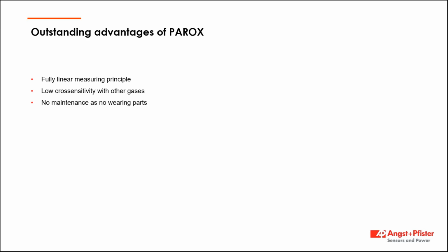Of course, you need calibration from time to time, but this very much depends on your application. You have a very long lifetime. When a sensor is running in steady conditions and with well-filtered air, it runs for years and even tens of years. You have precise measuring in the volume percent range. If you are looking for a real ppm application, then this is not the right instrument to use. But for a volume percentage range, it is really a good solution.